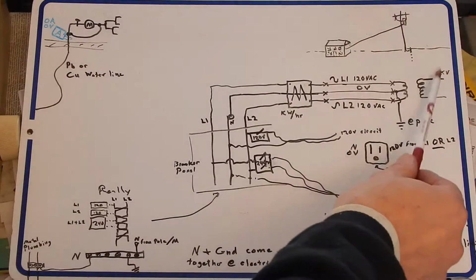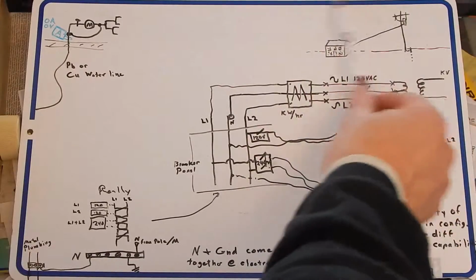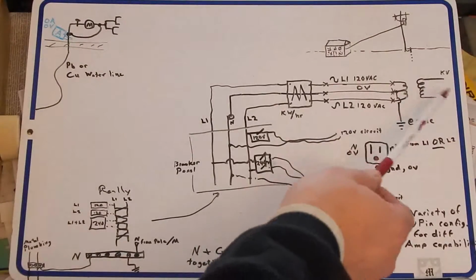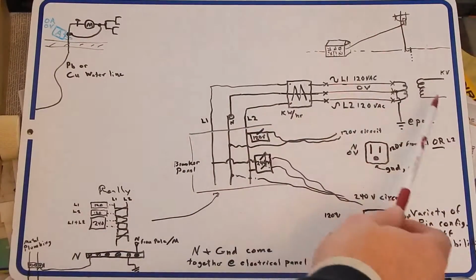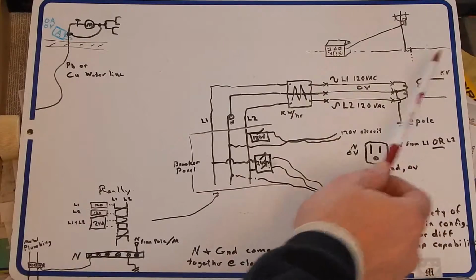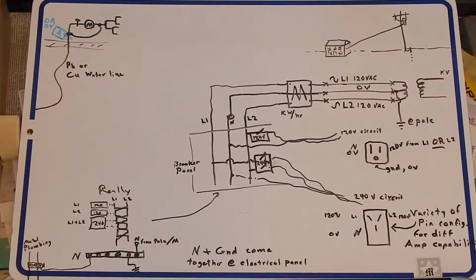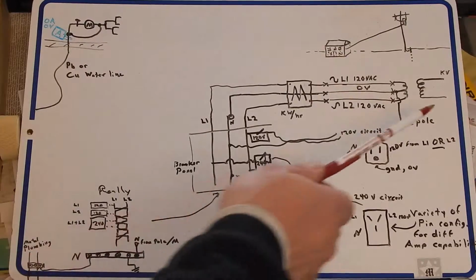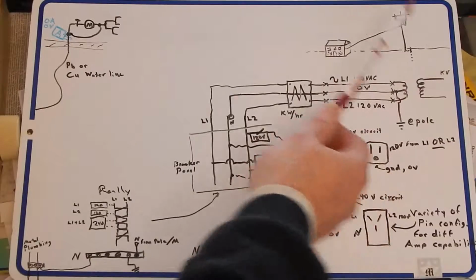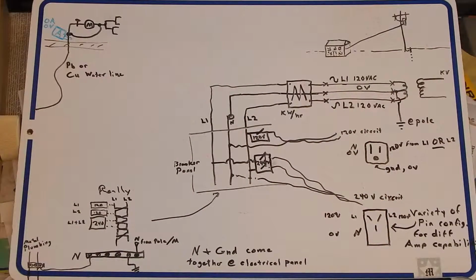So, coming off the main lines, it isn't the super high voltage, but it's a voltage they use around the neighborhood to connect several small transformers up. And it'll be in the kilovolts. It'll be as low as 5 kilovolts or as high as in the 30s. It all depends on the electrical company that's doing the work. They're not all the same. I know I used to live on the other side of the state, and almost everything was 12.2 kilovolts. But I know around here it's different. I don't think they even use 12 kV that much.